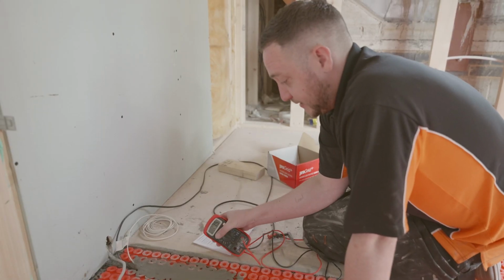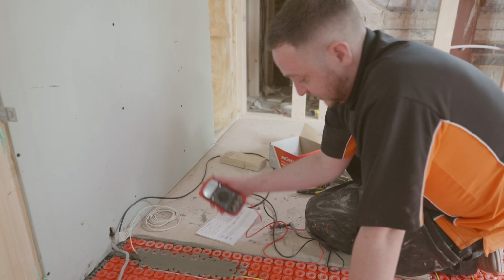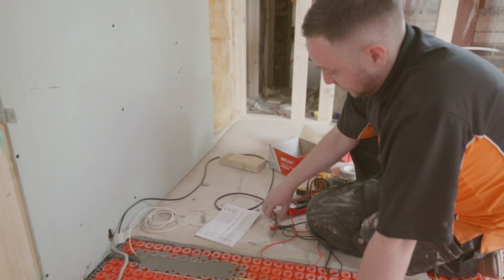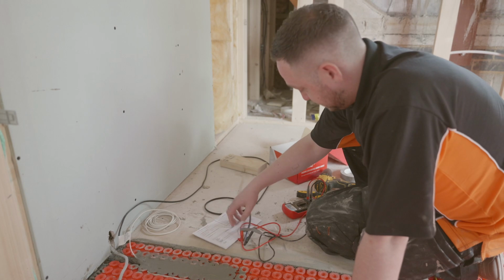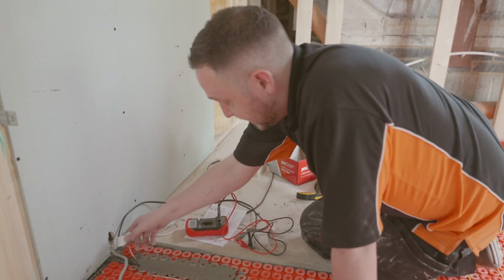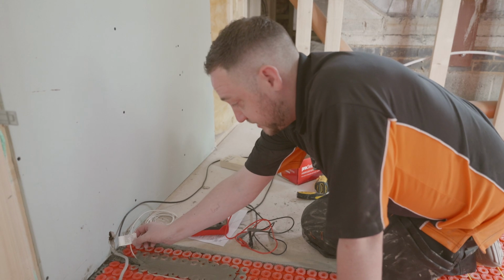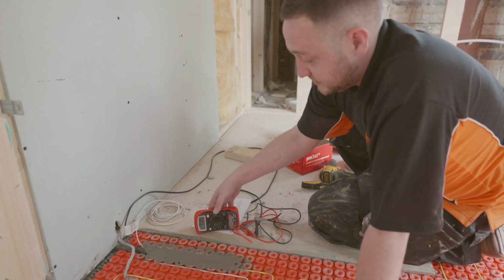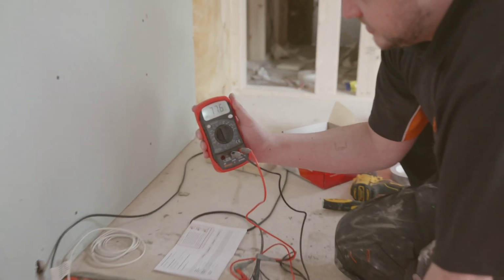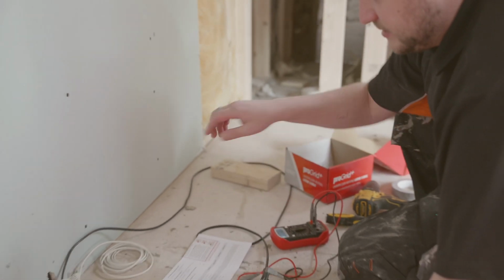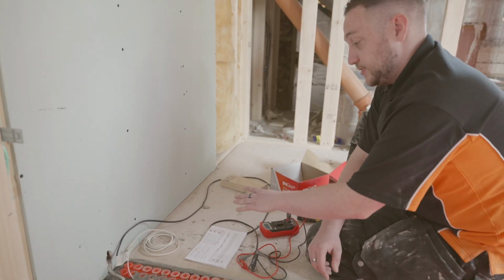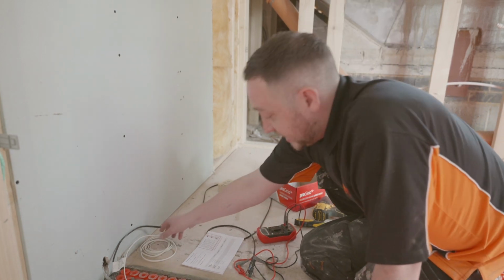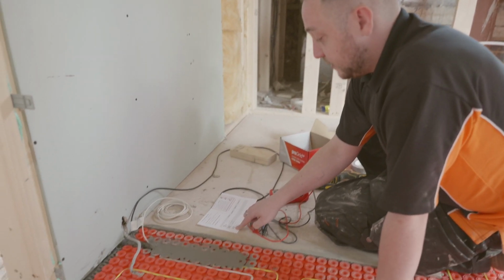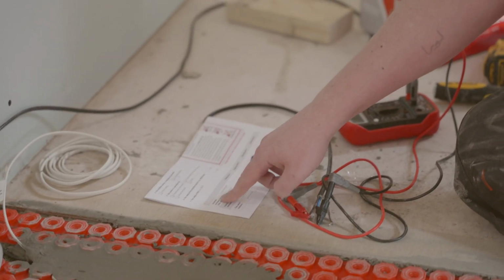The last thing that we have to do now is just our final resistance check. So as you can see, we've got our crocodile clips hooked onto the cold tail of the cable. We know that we should have 78.37 ohms or within 10%, and we're currently sat at 77.6. So this is all good. The last thing that we're going to do while we've got our multimeter out is we're going to check the resistance of our floor sensor, because it does ask for that on the commissioning record, and the insulation resistance test the electrician will do upon final connection.